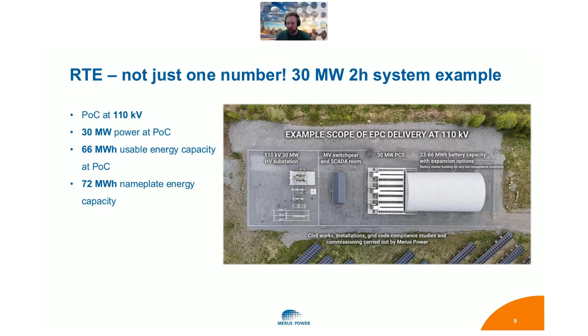We don't have time to go into this in detail, but here is just an idea of where the losses of this kind of system in a round-trip event take place. You have to consider the cabling losses, transformer losses, and auxiliary power use that is heavily dependent on the operation point. If you think of the operation of cooling systems, for example, the point of connection and the time and even the ambient temperature you are measuring the RTE with will heavily influence the outcome. The calculator that we will publish next month will show this in a transparent way.